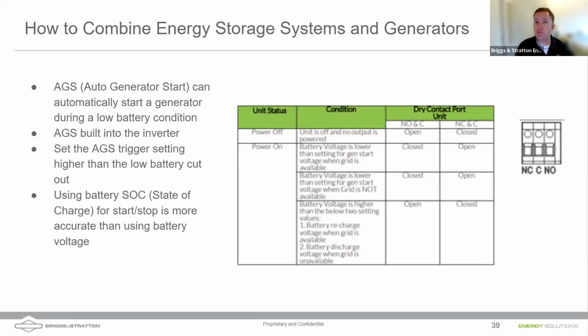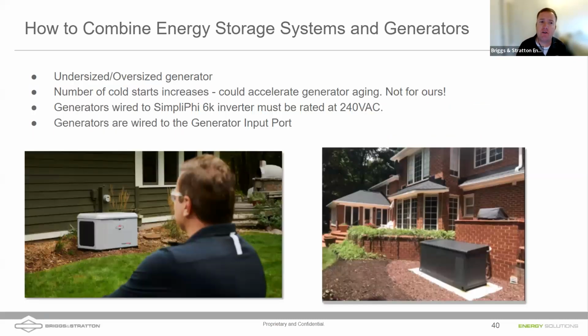If you do choose to use somebody else's generator, or already have somebody else's generator that uses normally closed, that is capable of being controlled by our inverter as well. And again, what's happening is the inverter is taking over the commands to start and stop the generator based on the state of charge of the battery.